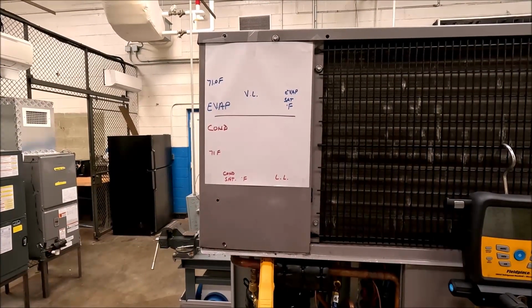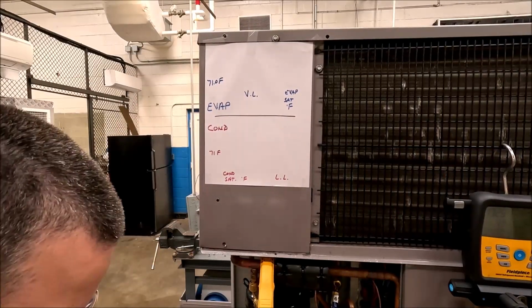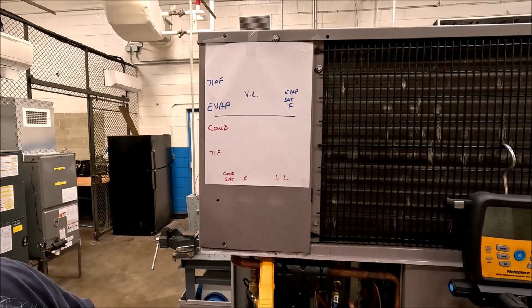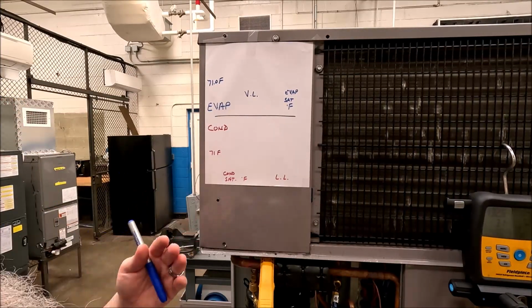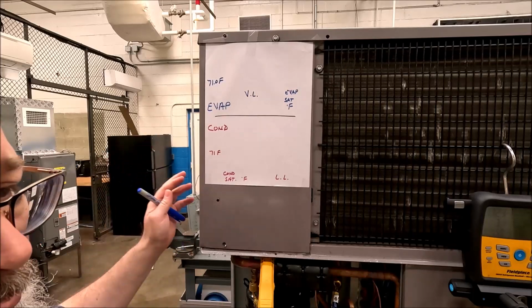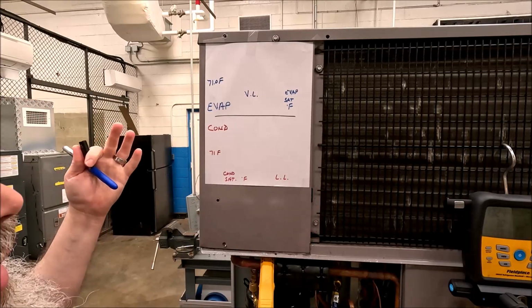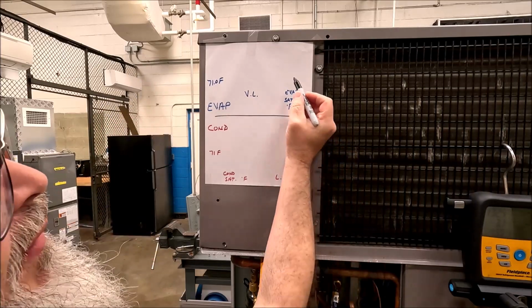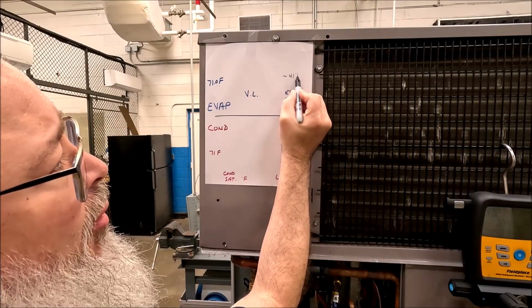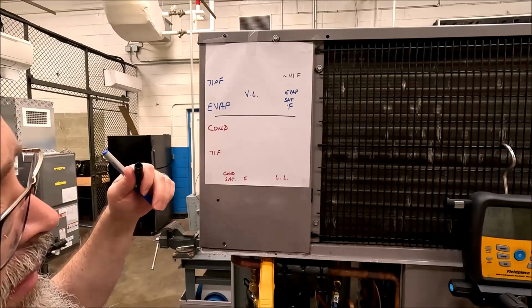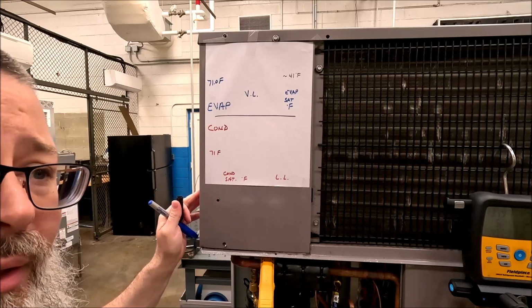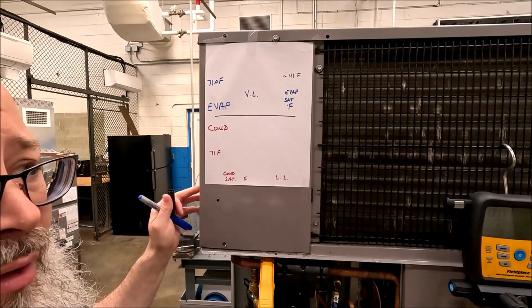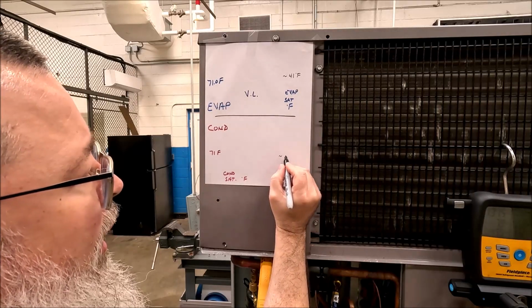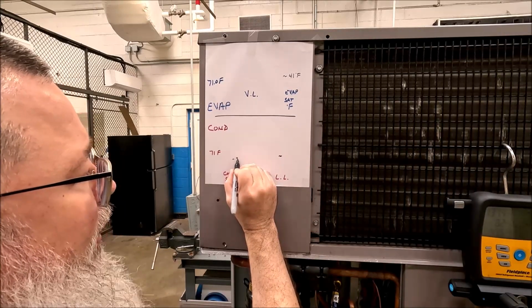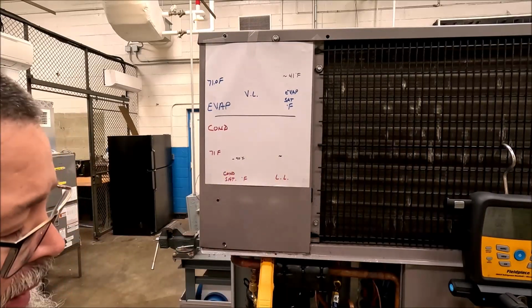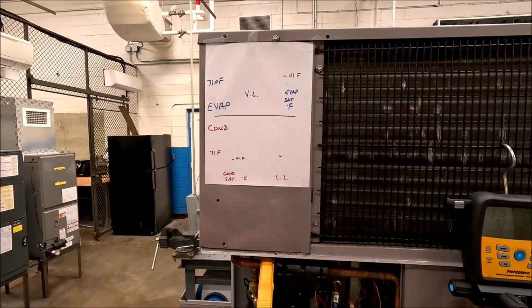Now what does that mean, once again, as we estimate what's gonna happen with our pressures and stuff? What are we looking for on the condenser? What are we looking for on the evaporator? Well, this is going to be another 410 unit, so I would hope that I'm about 30 degrees colder. So if I was, that would give me about a 41 degree evaporator. The SEER rating dictates the condenser. This one is a 15 SEER, so I would hope that I'm about the 90 degree mark, 91, you know, we'll say. So you won't know until you put your gauges on there.